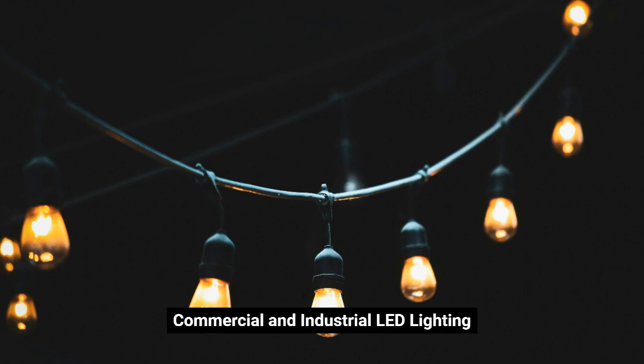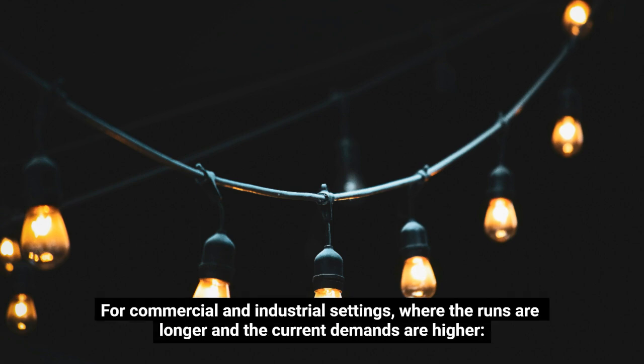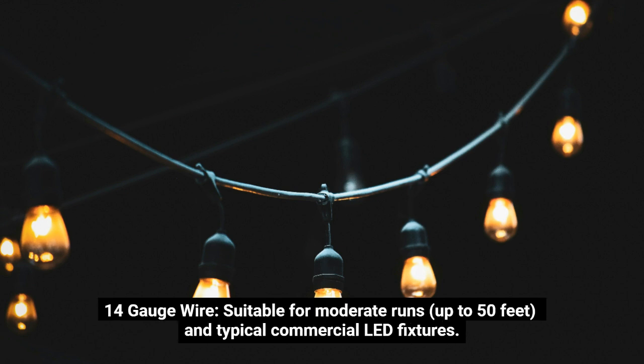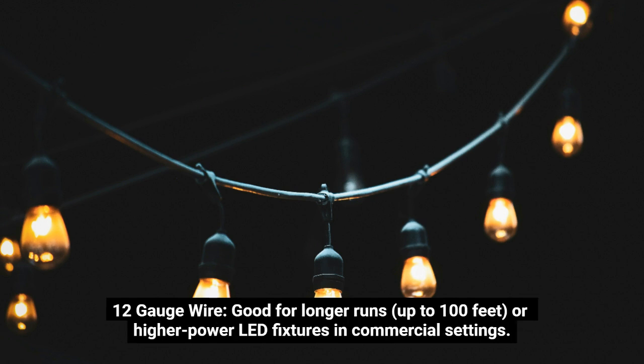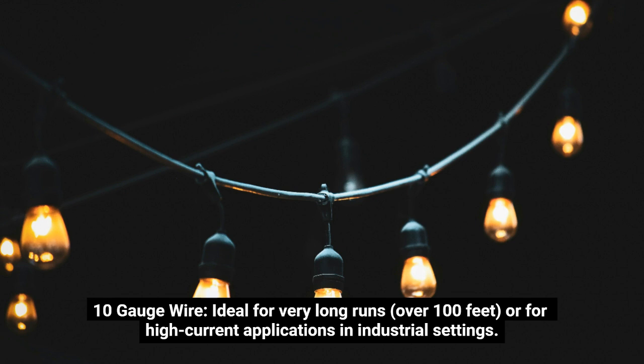Commercial and industrial LED lighting. For commercial and industrial settings, where the runs are longer and the current demands are higher: 14 gauge wire, suitable for moderate runs, up to 50 feet, and typical commercial LED fixtures. 12 gauge wire, good for longer runs, up to 100 feet, or higher power LED fixtures in commercial settings. 10 gauge wire, ideal for very long runs, over 100 feet, or for high current applications in industrial settings.